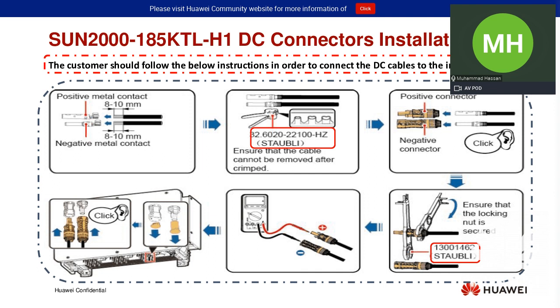You need to purchase it from the local market, and always purchase two tools, so that you can hold the plastic connector with one tool, and with the other tool you can revolve and tighten the nut. And don't leave any kind of gap or any threads showing on the plastic connectors. Otherwise, if you leave any gap, then there will be a problem for you in future because of ISO faults or some other issues, and you can lose production from those faults. Also, when you connect the DC connectors onto the inverter side, on the bottom of that inverter, you will hear the click noise again, which means the DC connectors are properly fixed to the DC input connectors of that inverter.